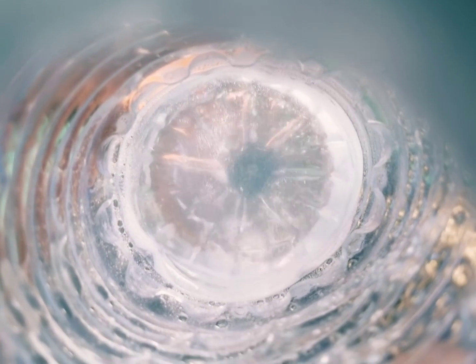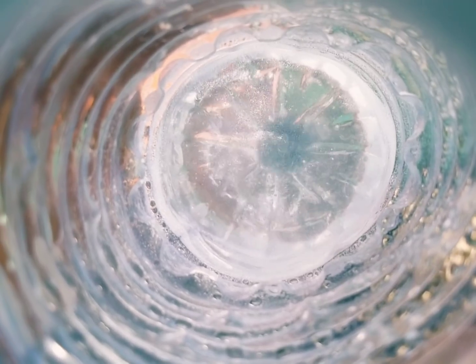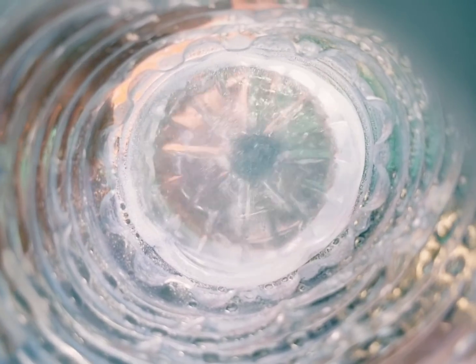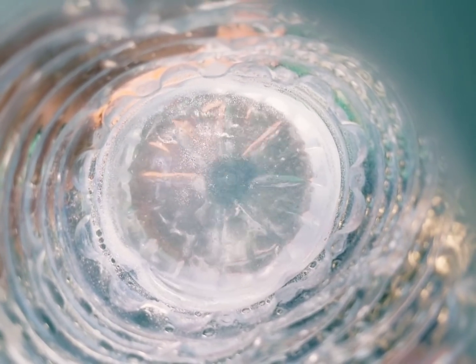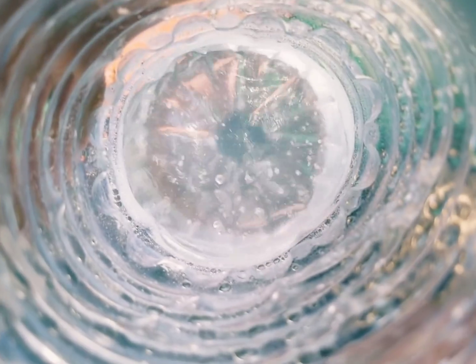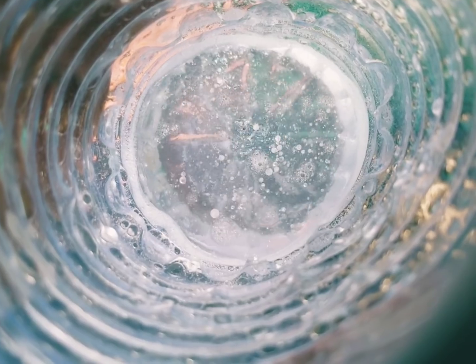This is about four days later. I was gonna check it at 24 hours but I haven't had time because a digital scroll has been giving me a lot of grief. We got it back up and running finally, so I'm back to my bottle of AC Smart Seal and water. As you can see, there's nothing hard inside — we just have the oil and water separating.